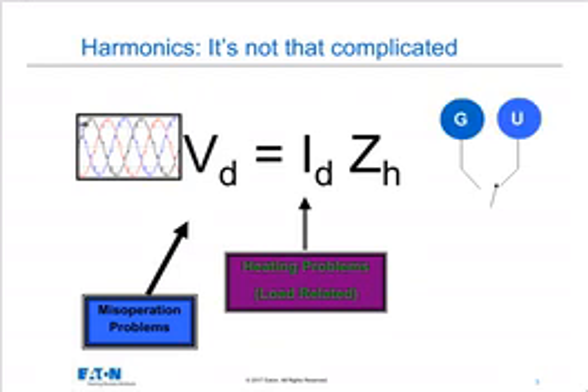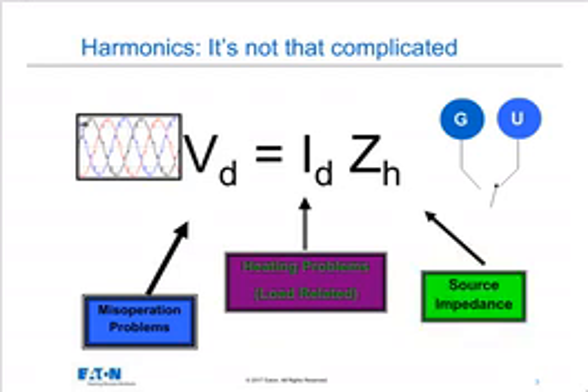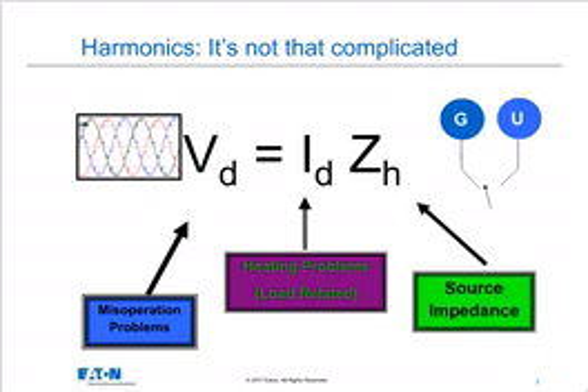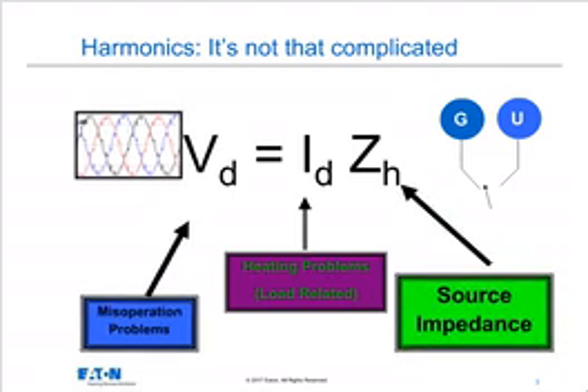Now a third thing comes into play, which is that we rely on the utility source as our primary source of power, but in fact, when we switch over to the generator, the source impedance can become significantly higher. So a normal utility source transformer might be 5.75% impedance. We switch over to the generator, and it's something on the order of 18% impedance. So the ZH here, the harmonic impedance, may be as much as 3 times the amount of impedance, and of course then with that, the voltage distortion grows significantly.